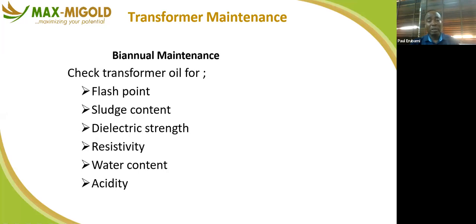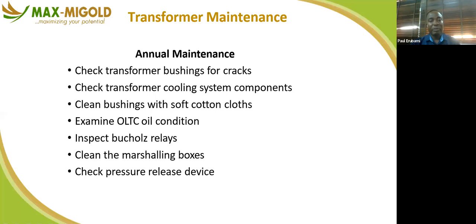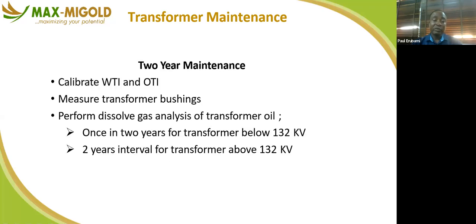So we have biannual maintenance. These are the things you check: the sludge, dielectric strength, resistivity, water content, and acidity. We have annual maintenance. These are the things you check when carrying out annual maintenance. We also have two-year maintenance: the winding temperature indicator and oil temperature indicator. You check these every 2 years.